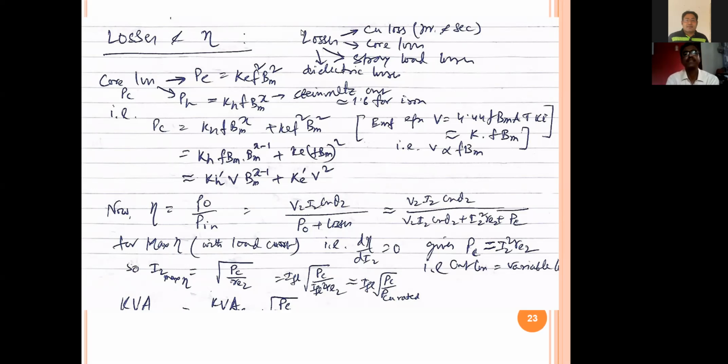So there you have some dielectric loss, because there is a magnetic potential in that transformer winding and core, and then you have zero potential there, and between them there is a conduction. So the dielectric losses are there. Then if you categorize the loss, copper loss is the most in a transformer, then comes the core loss. Now, if you formulate total loss as 100%, copper and core loss will constitute around 90 to 95% of the losses.